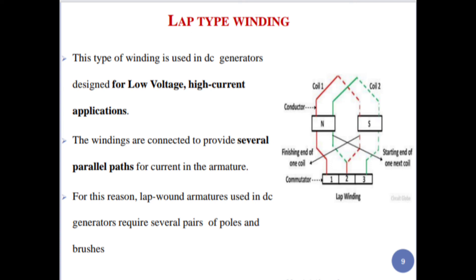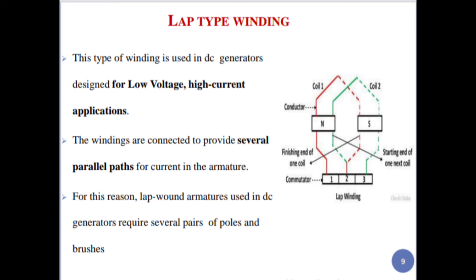Lap winding is used where low voltage and high current are required. The windings are connected to provide several parallel paths for current in the armature. The first coil finishes and the second coil starts from that point — this is the commutator connection. The finishing end of coil one connects to the starting end of the next coil. A lap-wound armature used in a DC generator requires several pairs of poles and brushes.